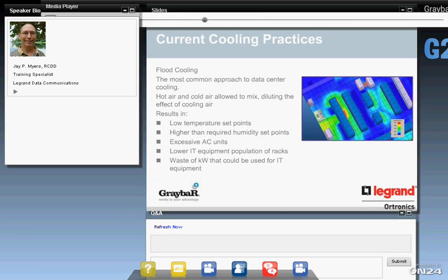Kind of a hidden cost is also humidity set points. The cooling naturally dehumidifies the air, but the common wisdom is that you need to keep the relative humidity up to about 50% to prevent electrostatic discharge, which can damage your equipment.